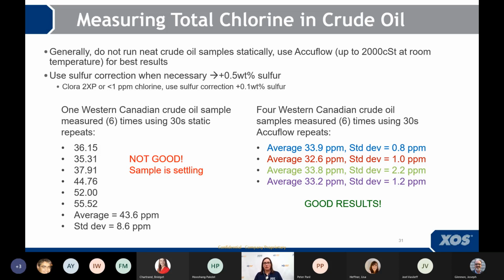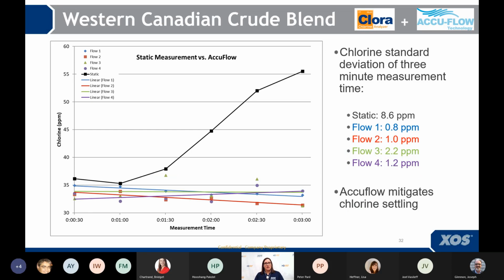And look how much this sample settled. The standard deviation, not so good. So one of the things you can do is consider using AccuFlow, okay? This is applicable for samples up to 2,000 centistokes at room temperature. And one note, when you're measuring total chlorine in crude oil, don't forget sulfur correction if the sulfur is above 0.5% sulfur. Let's look at this graphically, okay?